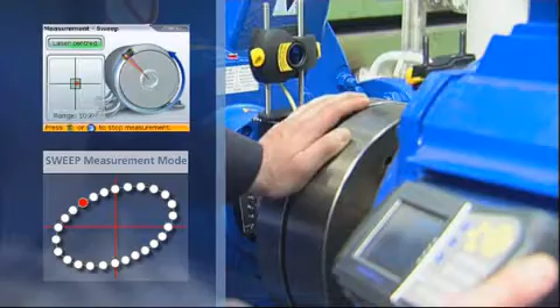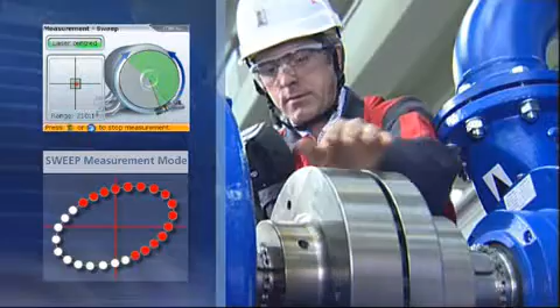After entering machine dimensions, measurement can begin. Simply rotate the shafts to take the measurement, starting at any position and rotating in any operating direction. During rotation, a large number of measurement points are taken automatically. A rotation of 60 degrees is enough for Optalign Smart to determine the precise alignment condition.